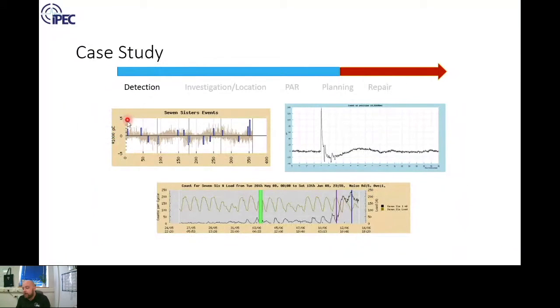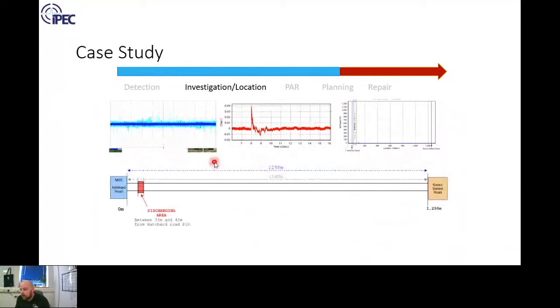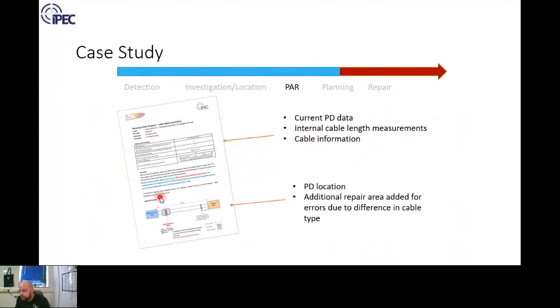Practical example then: PD monitoring - this is the individual PD segment, this is the load information. This is the PD level, and in this example you can see this PD increasing dramatically. We did an online PD location using that sort of method like I said before. Online PD location located to a 10 meter section on a 1250 meter cable. Issue a report to the customer to recommend action.